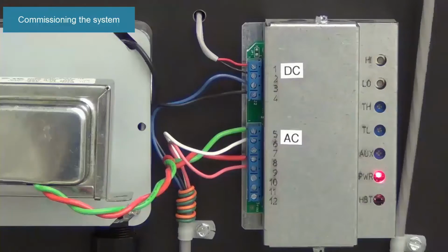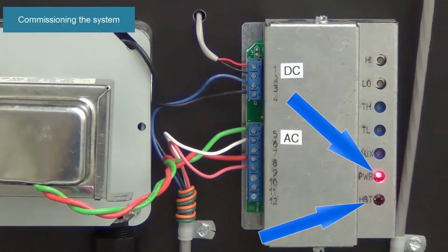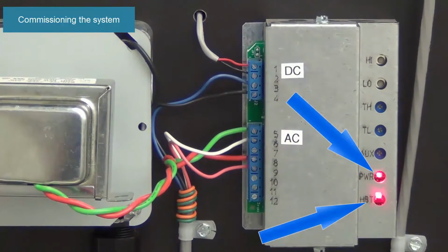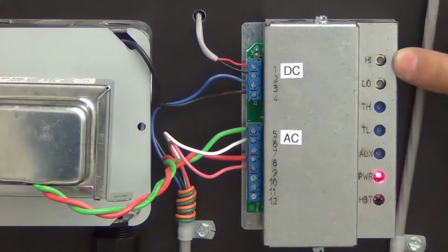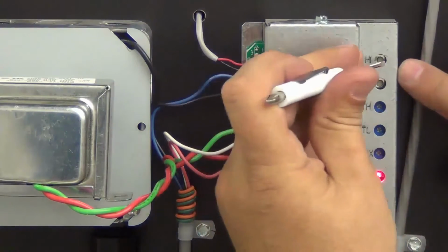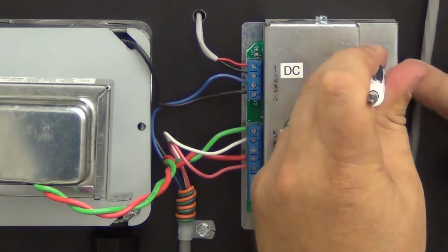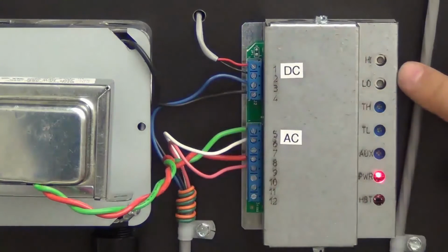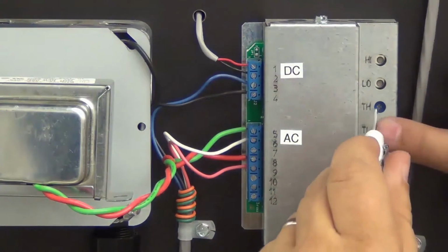Turn on the power to the exhaust fan, makeup air fan, and if installed, the heater. On the controller there will be a steady red power light and a pulsing heartbeat LED to indicate the control is energized and ready for programming. Turn on the exhaust fan to high. On the controller, push in the high button for a couple of seconds. Adjust the high trim pot to match the exhaust airflow.